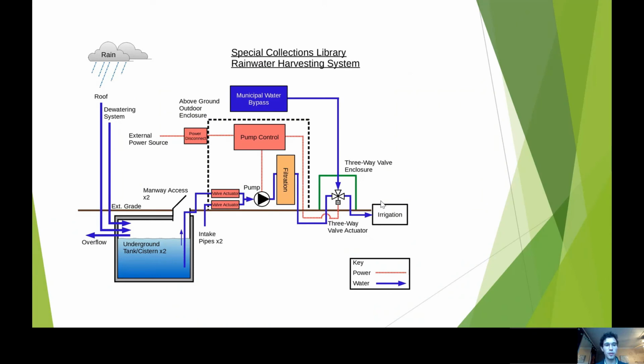I'm going to go over a drawing of the Special Collections Library rainwater system to give you all an idea of how this is supposed to work. Water you can see coming in from the roof and dewatering system into 2 below ground tanks and cisterns. These 2 tanks are not connected, so there are 2 separate intake pipes, which are pumped up by a single flooded external suction pump. In order to only pump from one tank at a time, there are 2 valve actuators that are controlled by the pump to decide which tank water is to be drawn from.